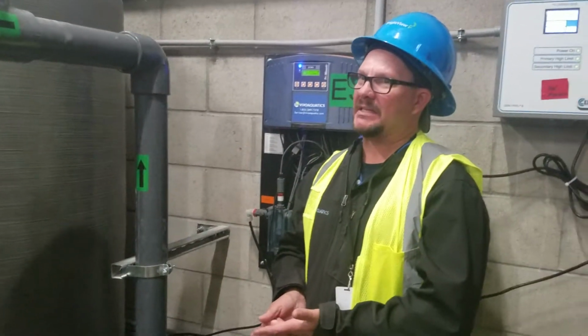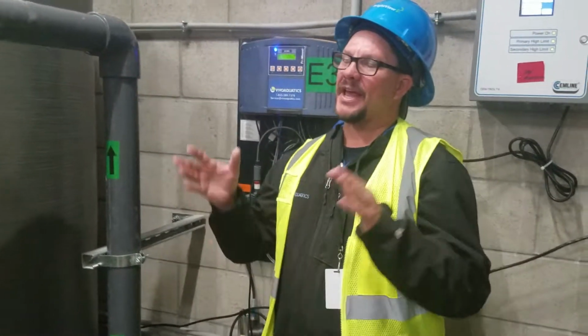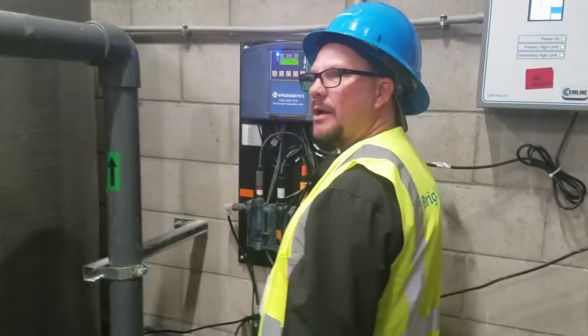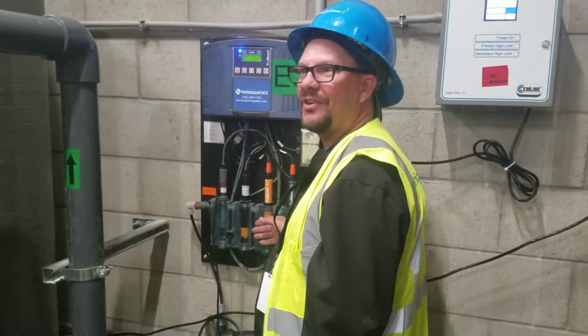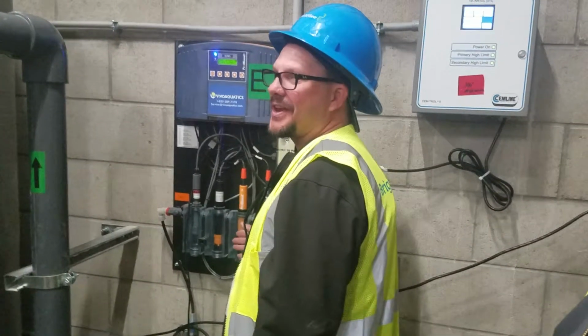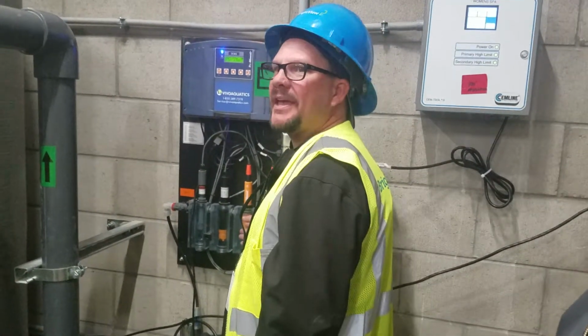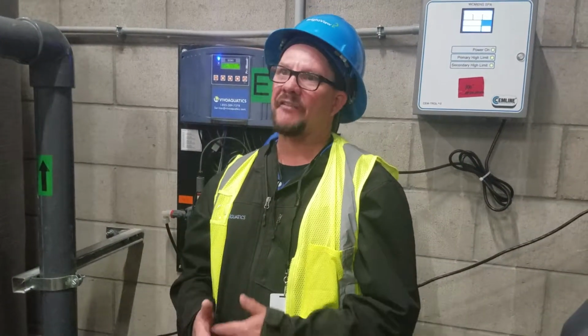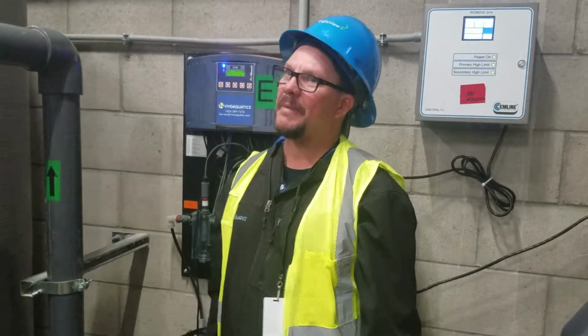If that happens, once you get everything back down to levels, you're going to want to go through a complete recalibration process of all these probes. You're just going to want to make darn sure that everything's back to normal. Don't be in a hurry just to turn these back on and walk away from it. There's going to have to be a little bit of monitoring going on manually.